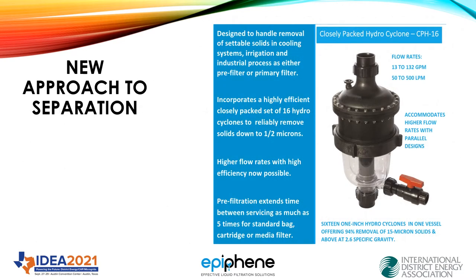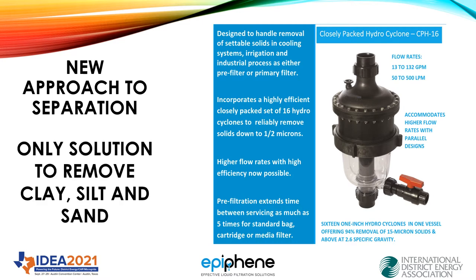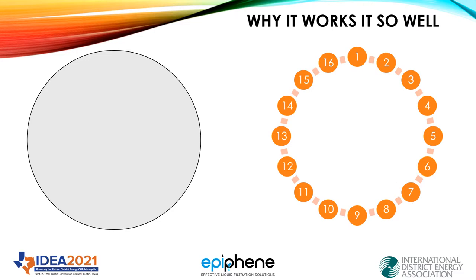So today we're going to look at a technology for separation that does a very good job on removing clay and silt, which heretofore has been pretty much impossible to remove. The separator itself is very simple. The water comes from the bottom. It's distributed across the plate with 16 radially placed 1-inch hydrocyclones. They separate out the dirt, and the clean water comes out the top.